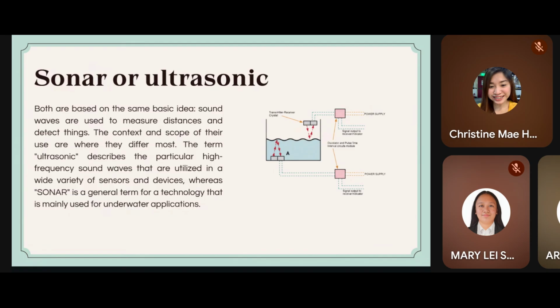Sonar and or ultrasonic. So it says here that both are based on the same basic idea. Sound waves are used to measure distances and detect things. The actual principle is that it uses high frequency sound waves, whether sonic or ultrasonic, that are reflected by the material surface. So, the device measures the time it takes for the echo to return, which gives the distance and thus the level of liquid or solid. Now, as for its frequency range, sonic devices are usually below 10 kilohertz, while ultrasonic are around 20 kilohertz.